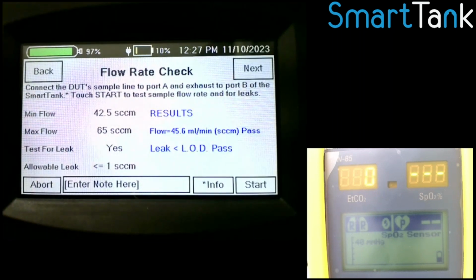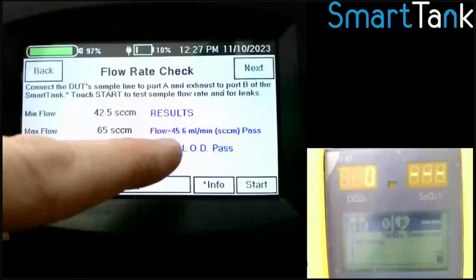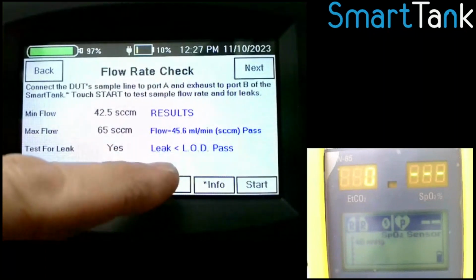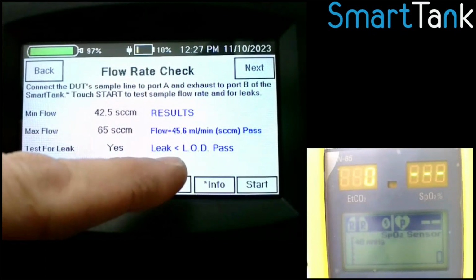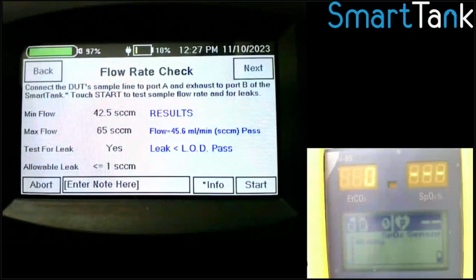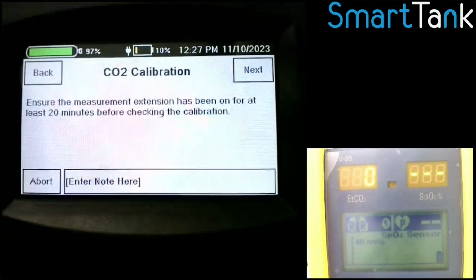All right, so it's finished. It measured a flow of 45.6, and the leak, it passed because it's less than our limit of detection, which is 0.5 milliliter a minute, which is a very, very small leak. And so it passed both of those. So we're done, that's all we have to do. If it failed, and there was a way to adjust the gain on the pump, which some devices have, it would walk you through that, but we passed, so we'll hit next.